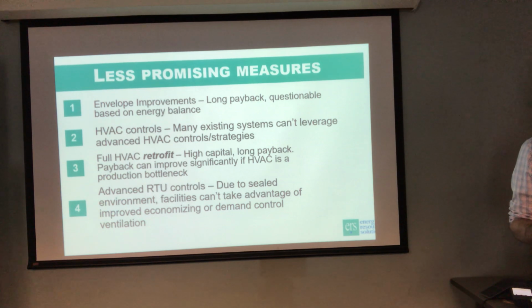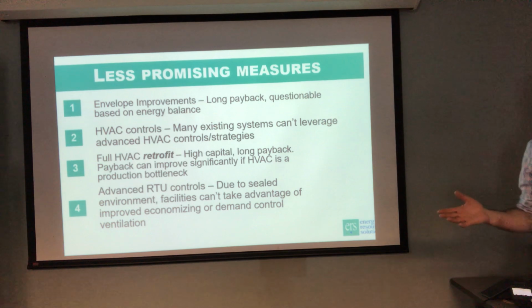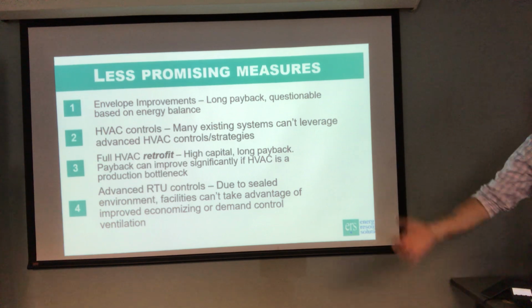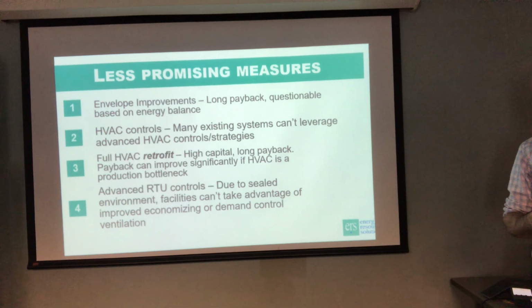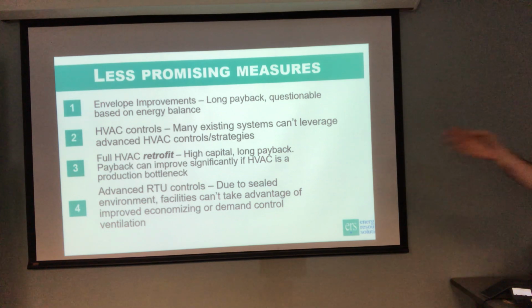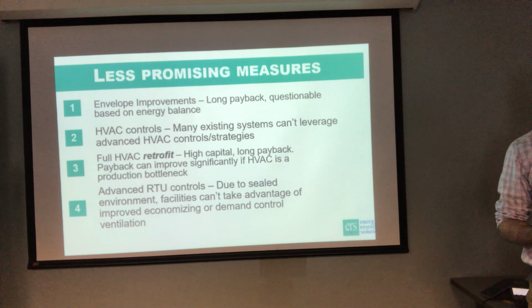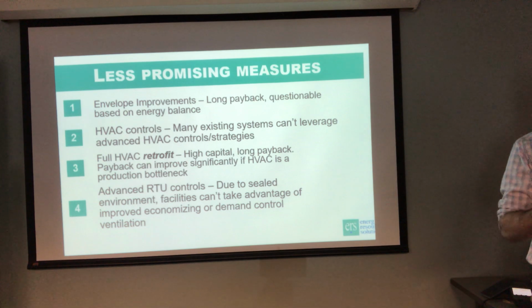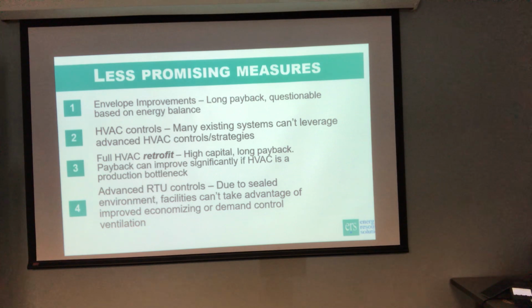With CO2 enriched atmospheres, that's not really a good fit for these facilities, right? If we start bringing in outdoor air, that means we have to ventilate the space, so now you're blowing all of your CO2 out the window. Another element of advanced rooftop controls that generates savings is called demand control ventilation. So this varies the amount of outdoor air brought into a space based off of the occupancy in that space as measured through carbon dioxide. Again, not really going to work in a room where you've got 1,000 ppm of CO2 and you don't want to bring in any outdoor air.